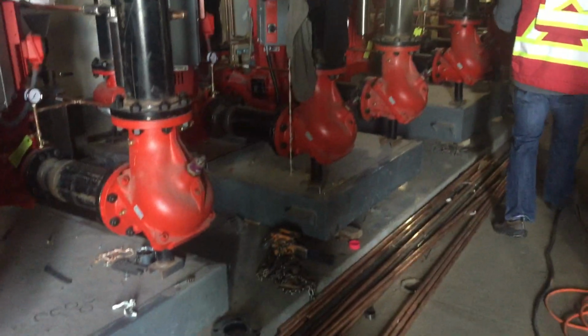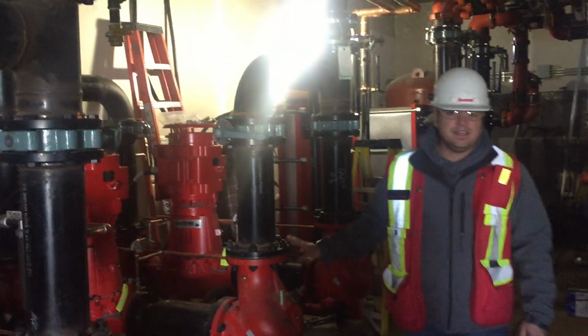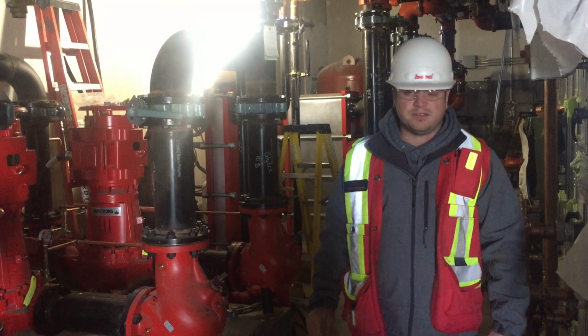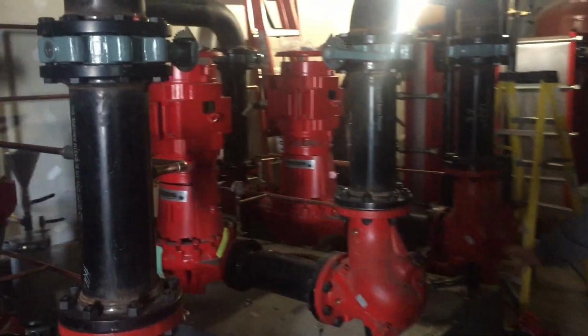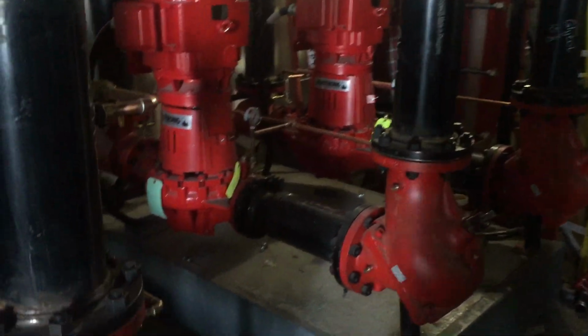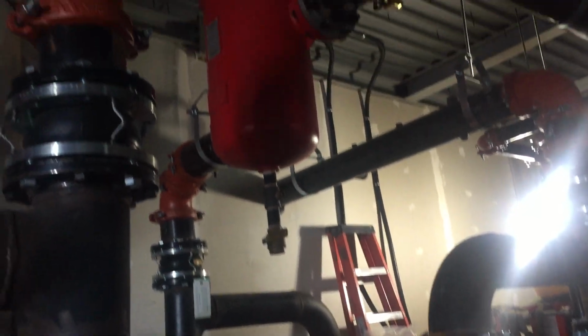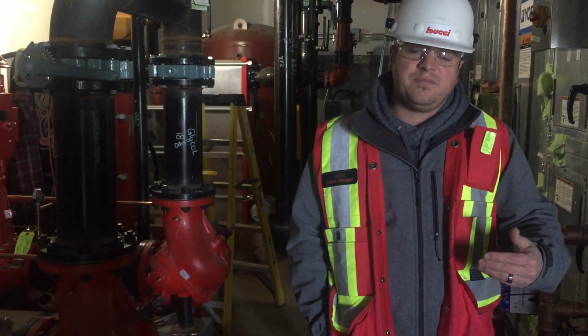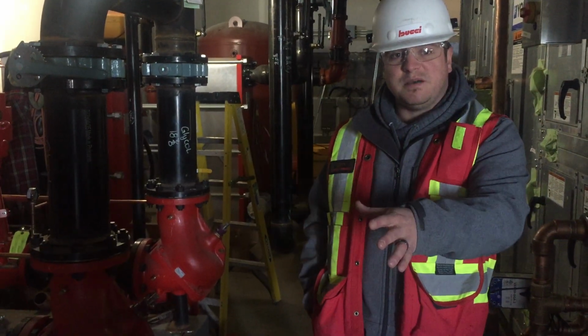So we come further down here, we have one more bank of pumps. And this bank of pumps here is for our condition side. So same as that, we got to push all the fluid through the building here. These ones here pull the conditioned water, the chilled water from that air conditioning unit that we just saw outside, and we push that through the building. So within each one of your homes, we have a 4-pipe fan coil, basically 2 radiators within that unit. Those radiators, one is intended for heating and one is intended for cooling. And they're fed from all of these pumps here.